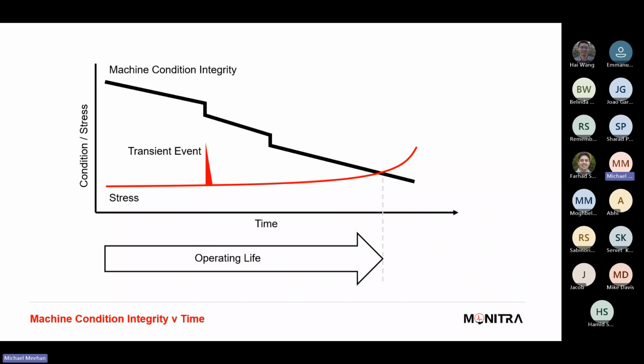When a machine is new, an event such as inrush currents or surges from breakers switching may be tolerated by the machine initially, but over time, those events can lead to potential failure when the strength approaches the stress levels. There's a high risk of premature failure due to the transients from those electrical surges or mechanical surges or other operating parameters which may exist. Contaminated winding left for too long, those sorts of things. The risk is greater when the machine does get old, as you approach end of life. So all of these factors are in play when people are considering how to look at strategies to remove those stresses from the insulation.